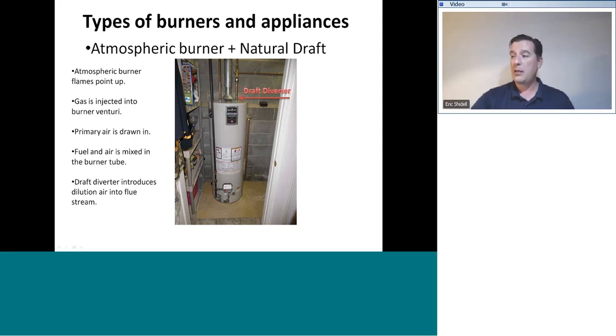That could be because this door that we had to open to get into the water heater area may be closed all the time and may be a solid door, not allowing that air to come in and draft upwards properly. Or it could be an issue with the flue as well. So combustion air supply and the vent both work hand in glove to create that movement of air up the flue. If you don't have the combustion air supply, we're also not going to have the draft, and that can lead to combustion problems as well.